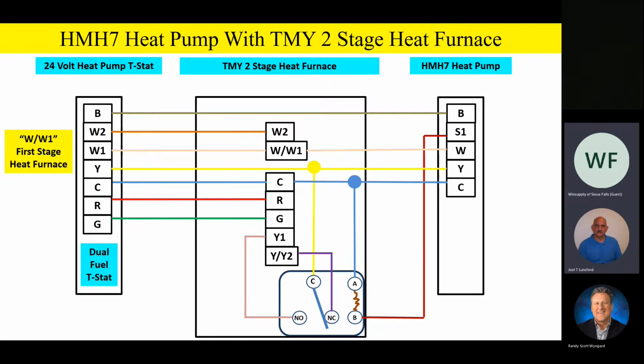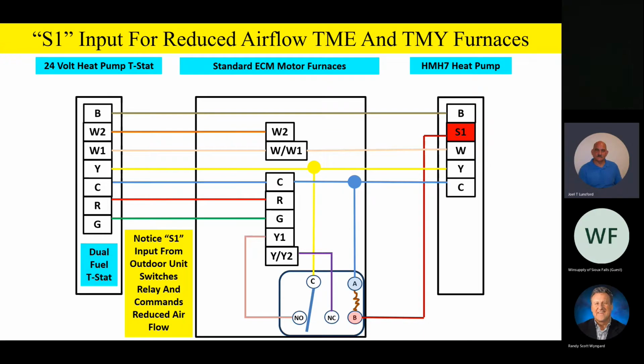Okay, sounds good. All right, so let's go ahead and do that animation. When we hit S1 on the outdoor unit, we're going to energize S1, and what it's going to do is switch that relay just like before and command low speed airflow. So just please remember the S1 relay, or S1 from the outdoor unit, is going to be your airflow reduction relay. And shortly, we're going to be looking at some variable speed products. And please remember the variable speed product is going to have the 002 kit. Now, the easy way to remember that, the 002 kit is going to have 2 relays on there, which we're going to discuss here shortly.